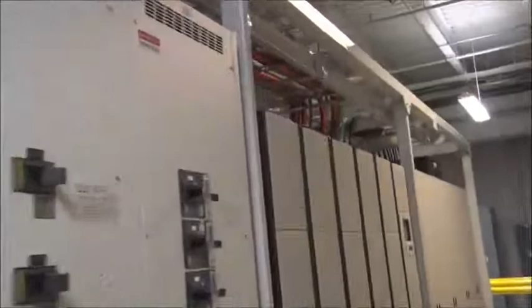And then the UPS, the value we're bringing with a prefabricated power solution is that we're doing all those interconnections in the factory. You'll typically have rows of cable tray above this solution with all the interconnections of the UPS, the batteries, and the switchgear. Ultimately the benefit is that once this goes on site, you're bringing the power in and the power out, and we're managing everything in between.